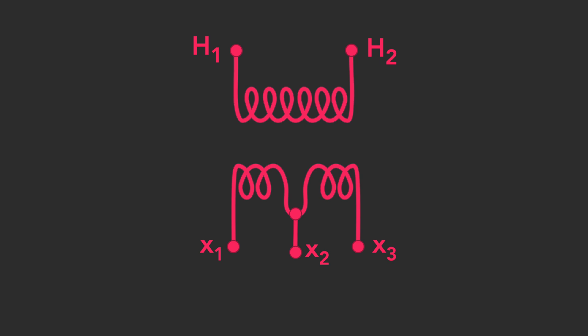In an additive polarity transformer, the winding A lead is connected to X3. The winding B lead is connected to X2. Winding C is also connected to X2. And finally, the winding D lead is connected to the X1 bushing. In this way, the windings are connected end to end or in series.